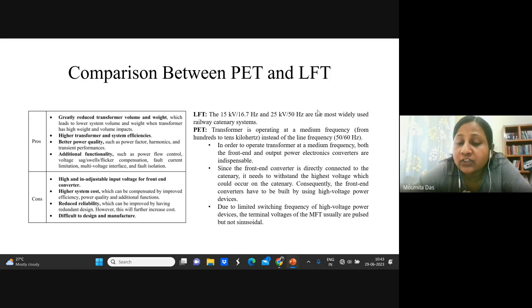But now the trend is changing due to the development of wide bandgap devices. So people can think of a high frequency transformer. That is why in the power electronics transformer, both medium frequency and high frequency transformers can come. So this can take a line frequency of 50 or 60 hertz.